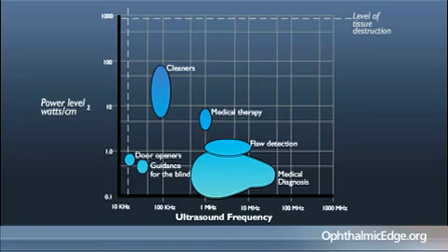But the ultrasound used in cleaners is quite high in its power level, watts per square centimeter. In diagnostic B-scan, we are using very low power levels, even lower than door openers or guidance for the blind. So you need not worry about causing tissue destruction when you're doing contact ultrasonography.